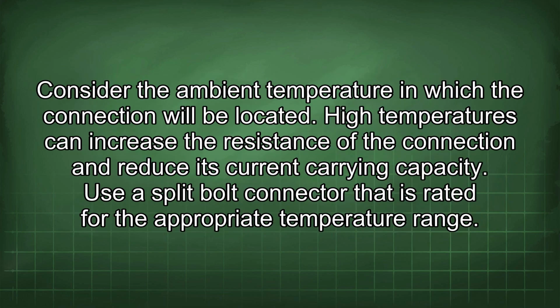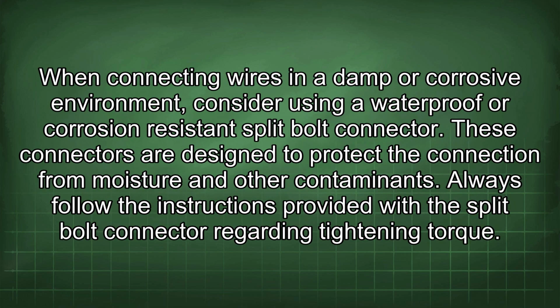Consider the ambient temperature in which the connection will be located. High temperatures can increase the resistance of the connection and reduce its current carrying capacity. Use a split bolt connector that is rated for the appropriate temperature range. When connecting wires in a damp or corrosive environment, consider using a waterproof or corrosion-resistant split bolt connector. These connectors are designed to protect the connection from moisture and other contaminants.